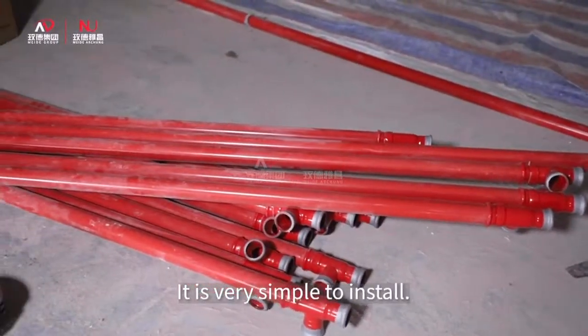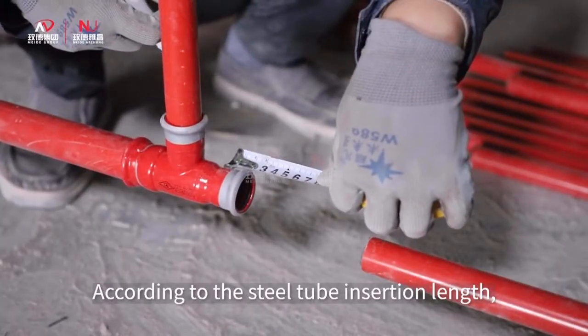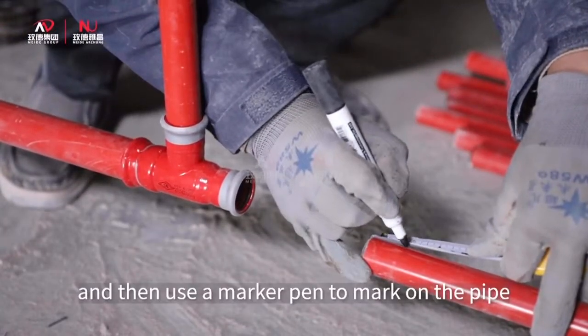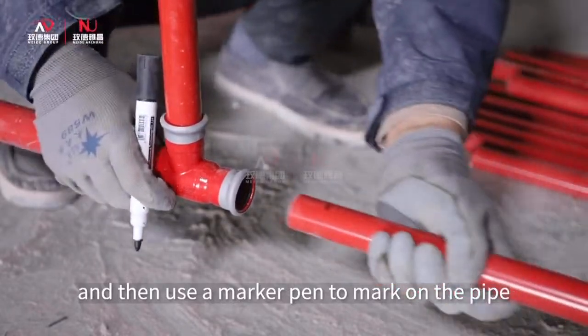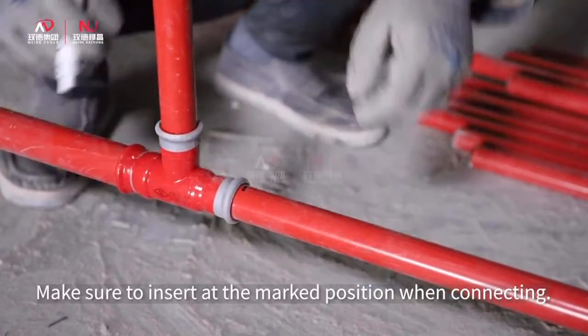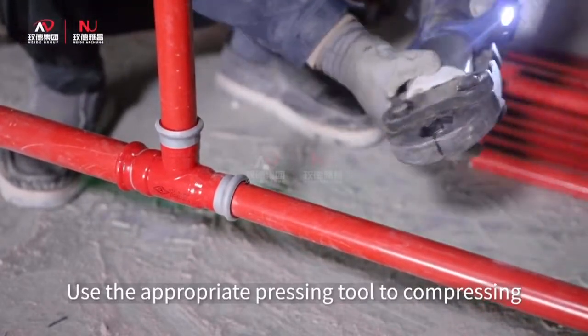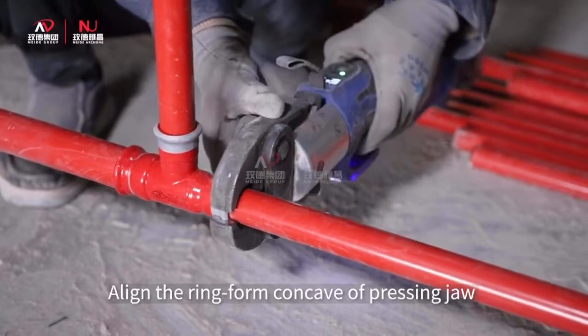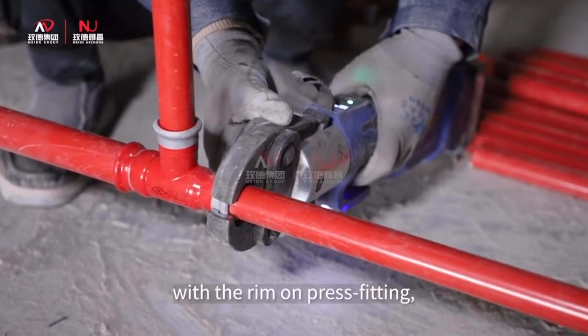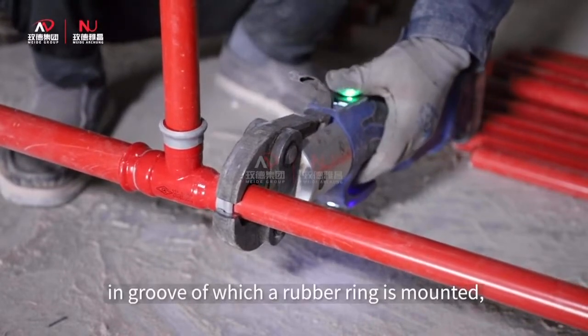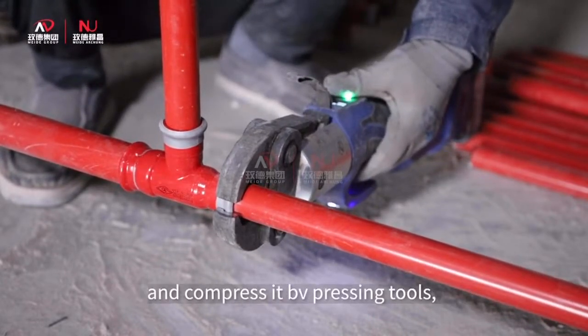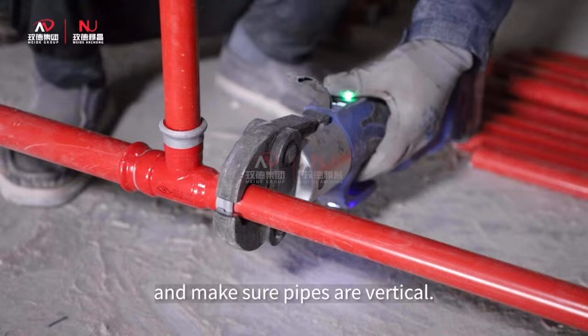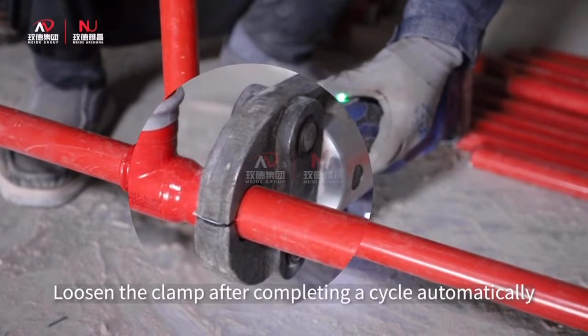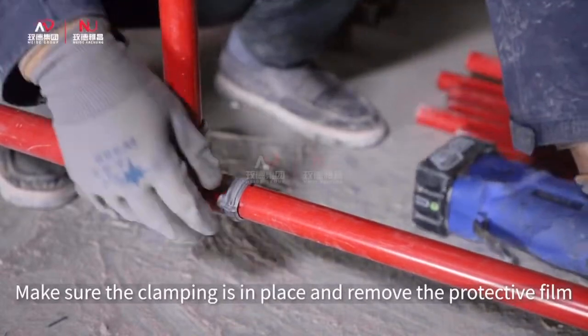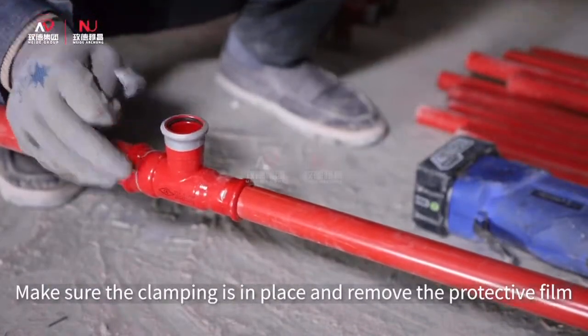It is very simple to install. According to the steel tube insertion length, use a marker pen to mark on the pipe. Make sure to insert at the marked position when connecting. Use the appropriate pressing tool to compress. Align the ring-form concave of the pressing jaw with the rim on the press fitting, in the groove of which a rubber ring is mounted, and compress it with the pressing tool. Make sure the pipes are vertical. Press the switch and compress, and the clamp loosens automatically after completing a cycle. Make sure the clamping is in place and remove the protective film.